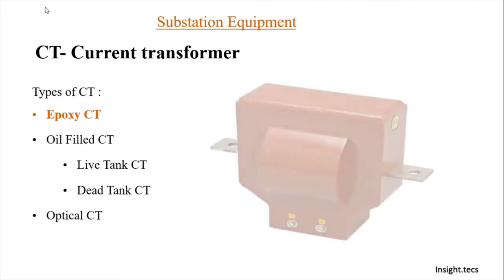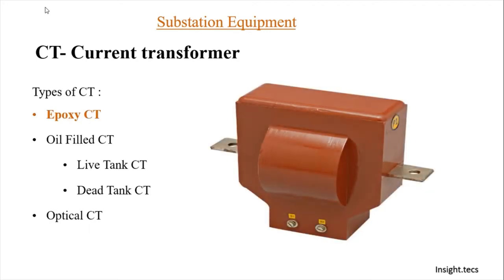Various types of current transformers. The first one is the epoxy CT, then we have oil filled CT, which can be further categorized as live tank CT and dead tank CT, and finally the optical CT. Let's understand what is epoxy CT. This type is generally used for 11 kV and below, and this type of CT is normally used where we have indoor bus.